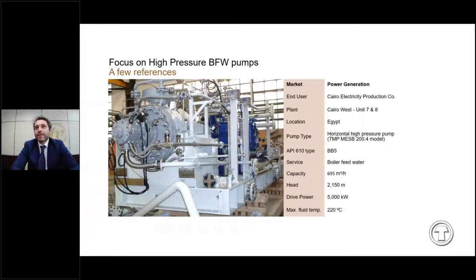Next, please. This is another application. This pump, like the previous one, is a BB5, so it's a barrel type. This pump was supplied around 10 years ago for a power plant in Egypt. The peculiarity of this pump is that it was for a supercritical thermal cycle. In fact, you can see that the fluid temperature is very high. We are at 220 Celsius degrees.